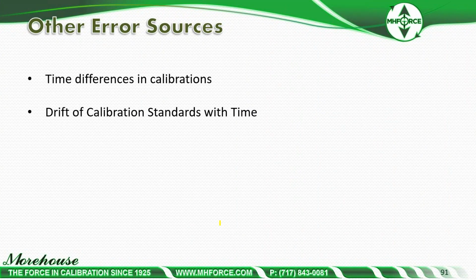Other error sources not covered: time difference in calibrations and drift of standard calibrations with time. So time differences in calibration is interesting. So the way you apply a force, I know what we do. We apply dead weight, and we apply it for 30 seconds. It's timed. We apply it consistently.